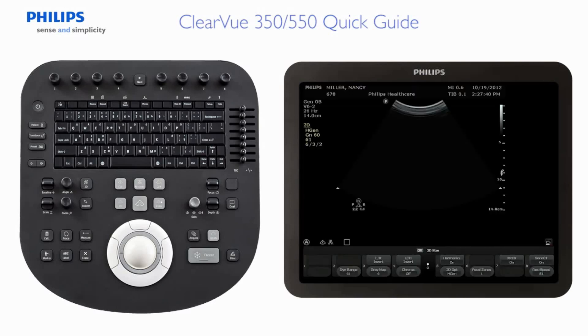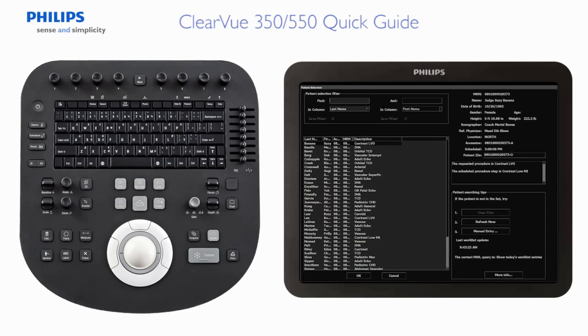Option 2: Use the Modality Worklist option if you are connected to an information system that allows you to select the patient from a pre-populated worklist. The Modality Worklist will automatically populate when the patient key is pressed.